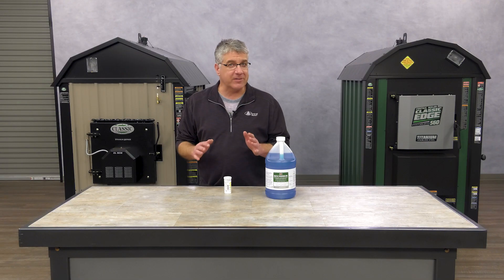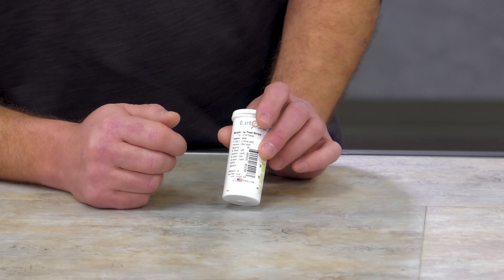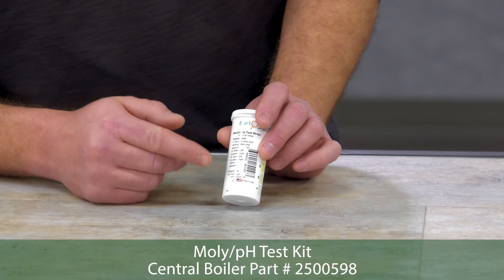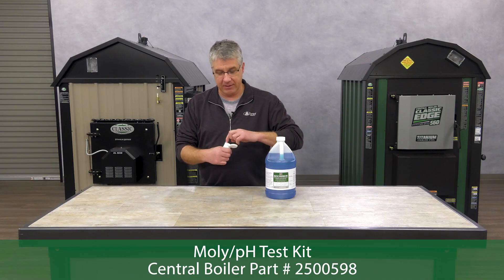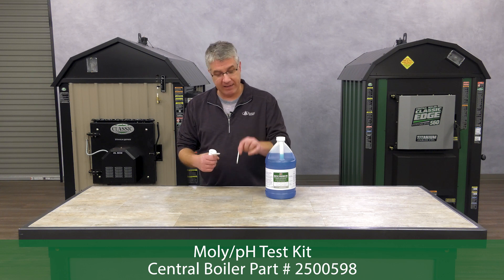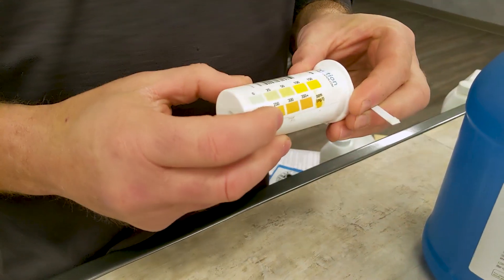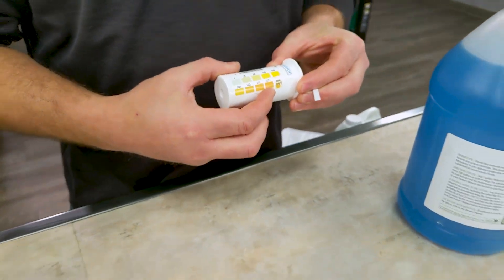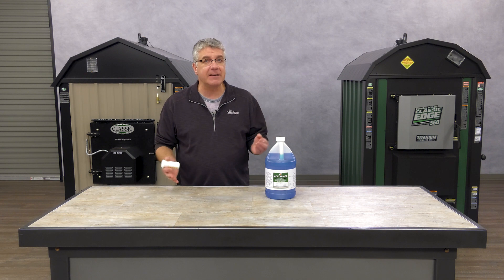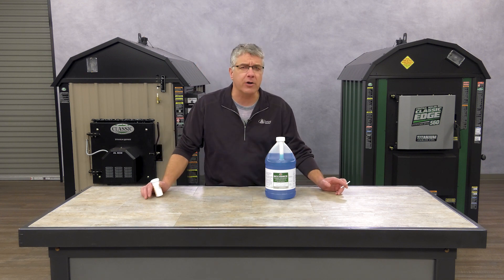After the system is circulated for about 24 hours, you need to make sure you have 350 parts per million. The way you do that is with these test strips. Notice there is an expiration date printed on the bottle. Take out one of the test strips, dip it in a water sample, and compare it on the chart. You want to have at least 350 parts per million. If you have more than that it's okay — it doesn't make any difference. You really can't add too much of Moly-Armor 350. It's a wonderful product.